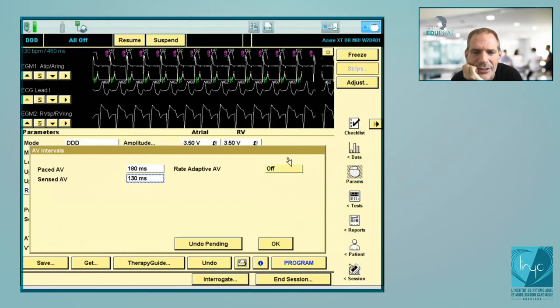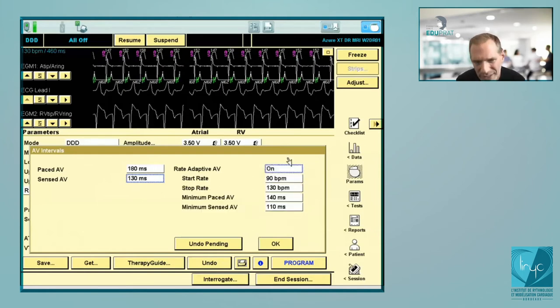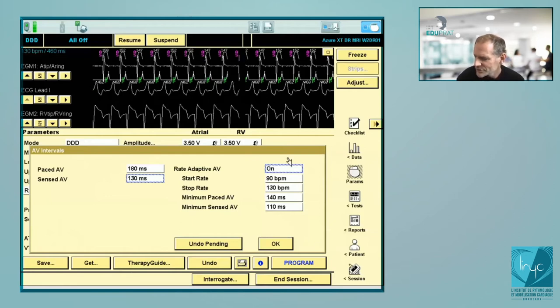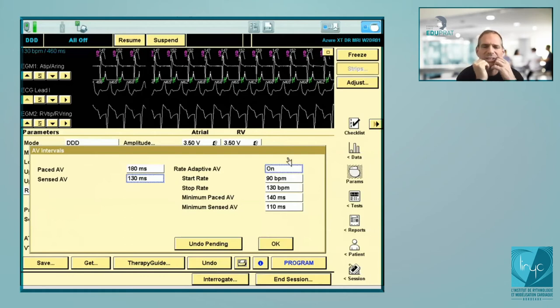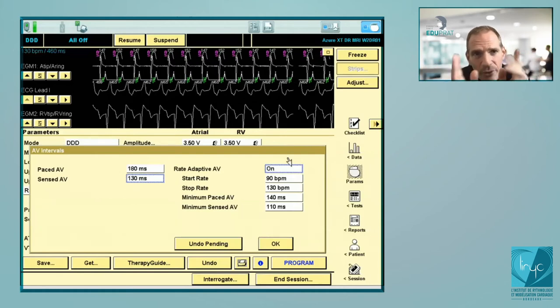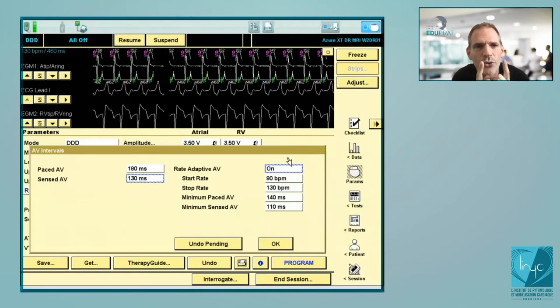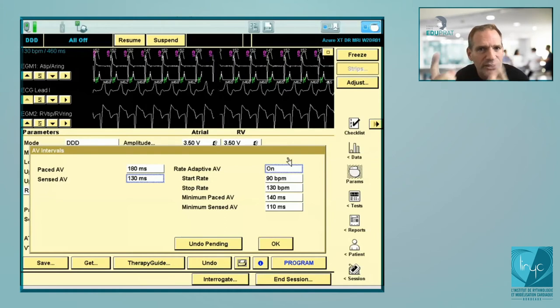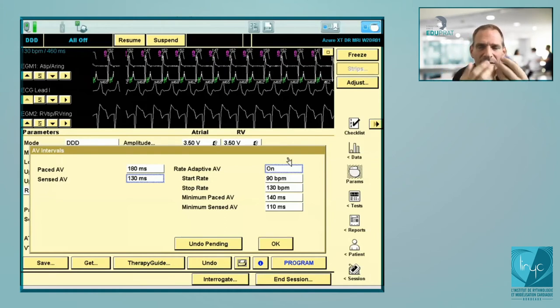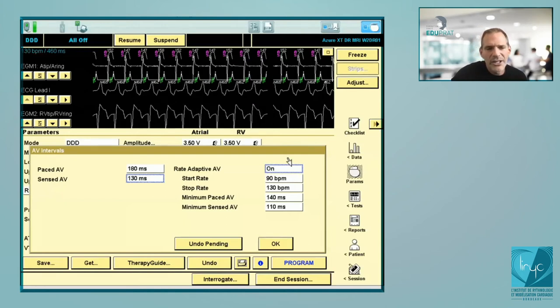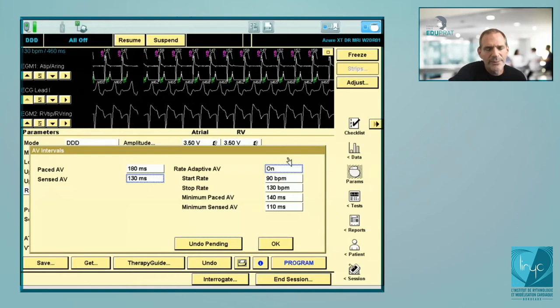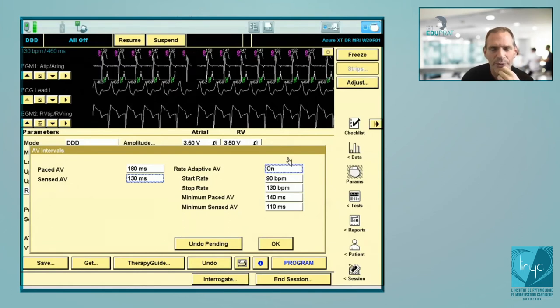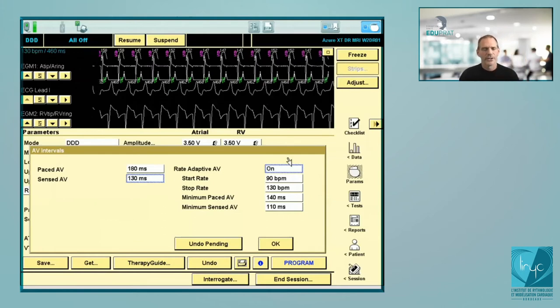If you program adaptive AV on, you have the possibility to decrease the duration of the sense AV delay when there is an acceleration of the atrial signals. So during sinus tachycardia, you decrease the AV delay considerably. Remember: the two-to-one point depends on the sum of AV delay and PVARP. The shorter the AV delay — particularly during exercise with faster heart rate — the lower the probability of encountering a two-to-one block. In a young patient, I will program 130 ms at rest and for example 90 ms minimum sense AV at the fastest rate.